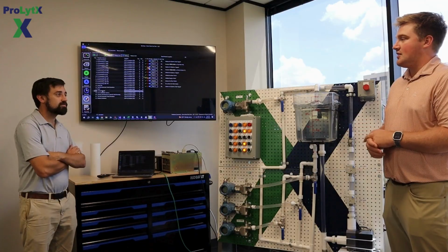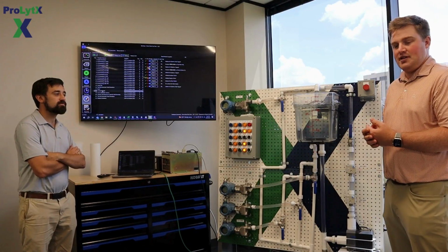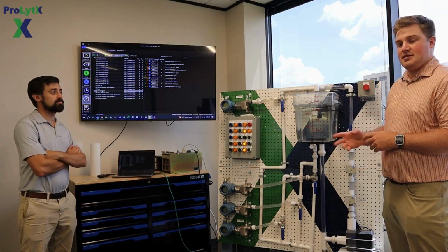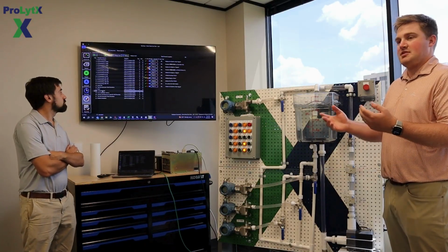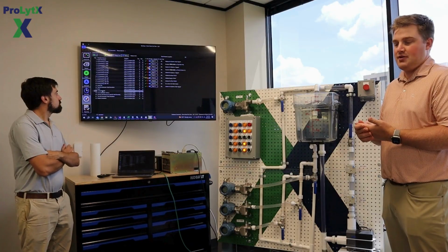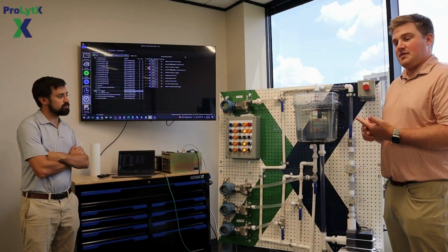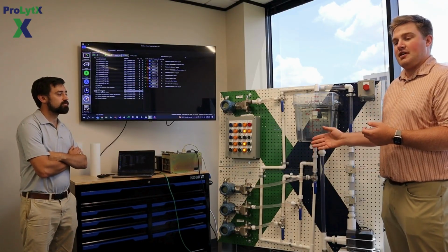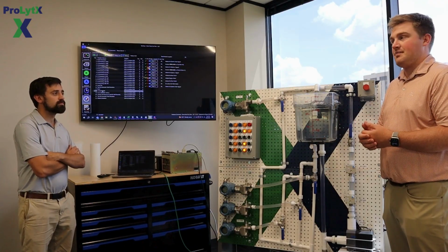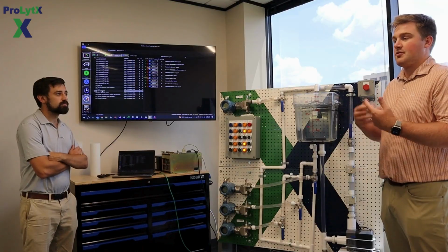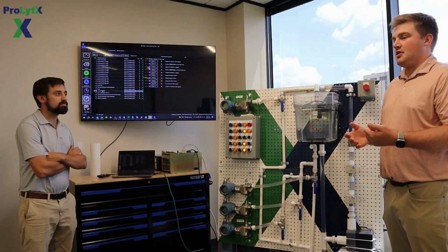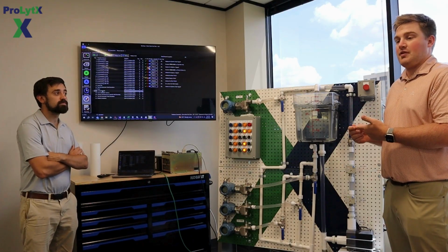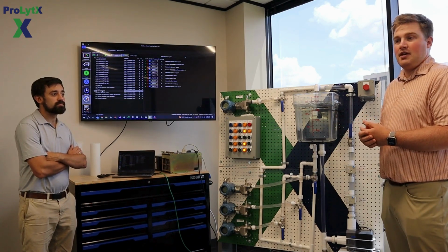So just a high-level overview of what this software does: our team will create a scripted procedure to test certain elements within a safety instrumented system, the logic. Our team will receive design documentation, mainly cause and effects and control narratives, along with the logic, and design a procedure to test and ensure that functions are carried out in the logic as described in the documentation. And without fail, every single project we do, we will return to the client some findings, which will often be discrepancies between the design documentation and/or the logic, and updates will always need to be made.